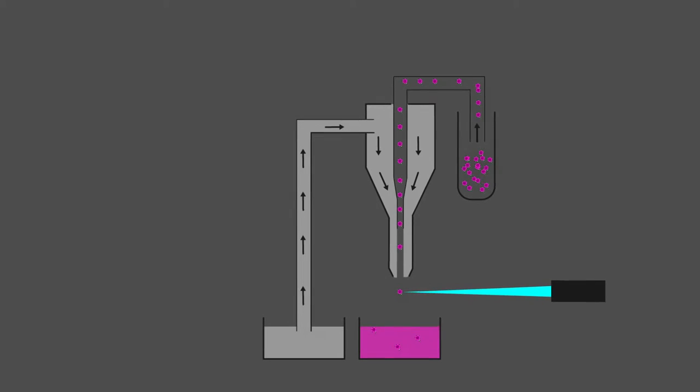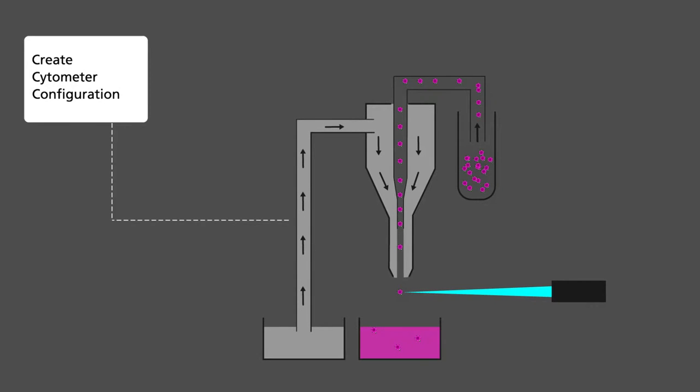The first thing we have to do is to set up the machine in relation to, for example, what type of laser we are using or what sheath pressure we have. This is normally done only once when we buy the machine and when we change part of the hardware and is called baseline setup.